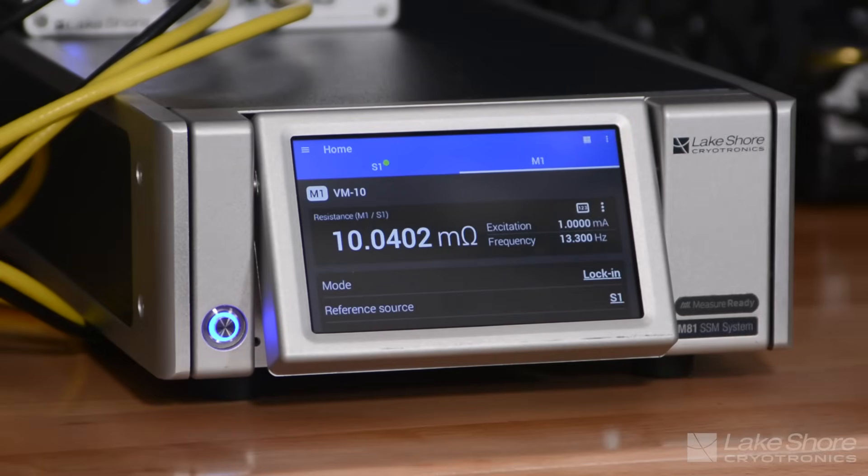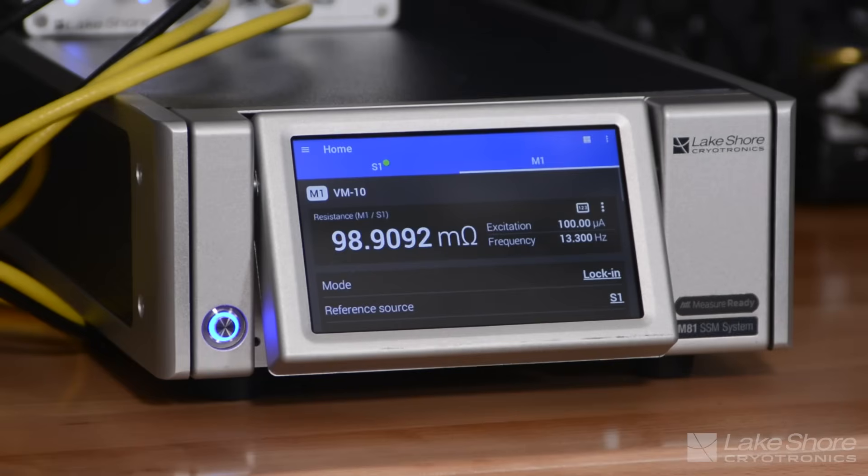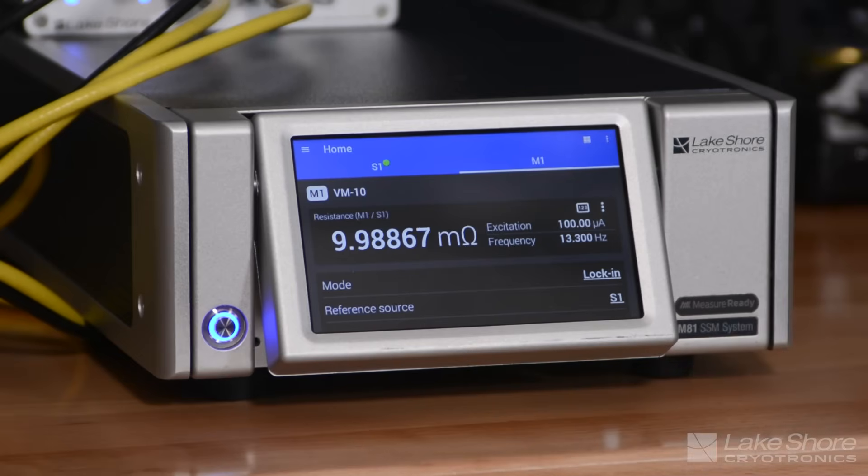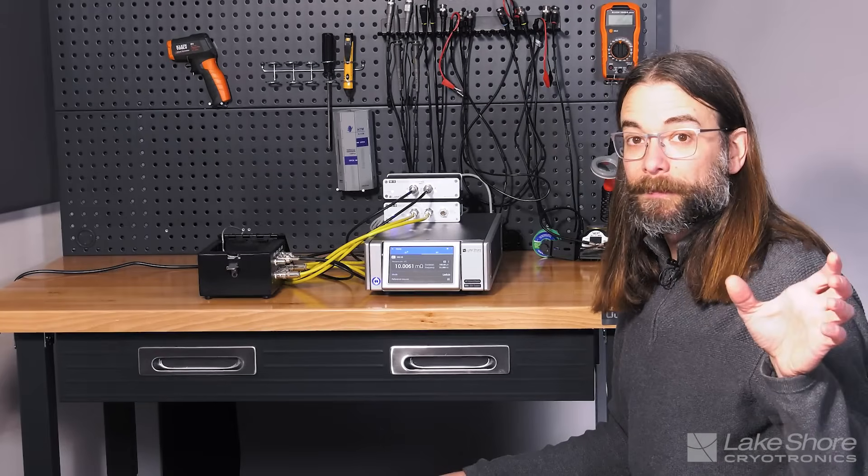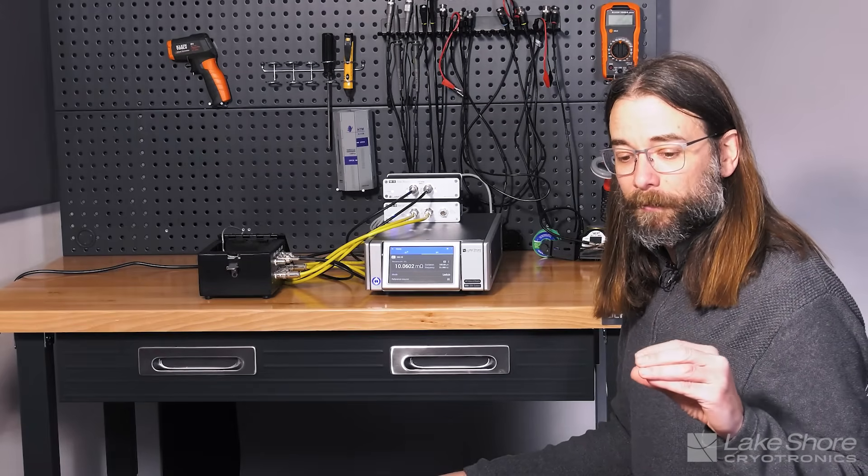But you can see now we're reading 10.04 milliohms, which is really an accurate reading for this particular device. And we're at 1 milliamp. So what happens if I drop it even further? Let's say I go to 100 microamps. And then we give it a little bit of settling time. And so now we're at 10 milliohms again. So we've started with 10 milliamps, where we had a fairly accurate measurement of that 10 milliohms.